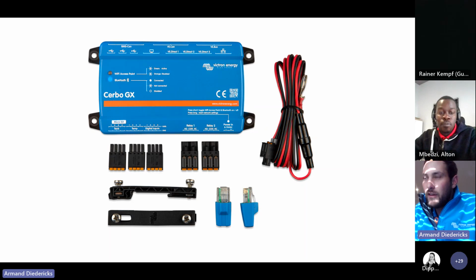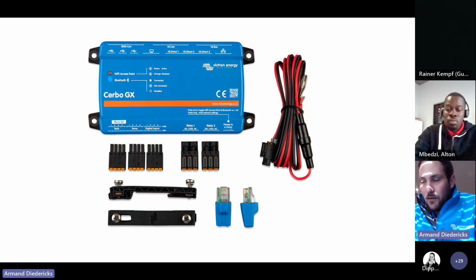Right, so you can see at the top you've got the BMS CAN interface, the VE.Can interface, the VE.Bus interface, the 3 USB connections. Then you've got your HMI display port, and then 3 VE.Direct ports, and then your Ethernet switch. If you have Ethernet straight to the inverter, or a switch as I mentioned on the AC coupled system, install AC surge protection, an SPD, on the switch, so that if there's a lightning strike via the communication cable from the ISP, it doesn't hit your Cerbo.